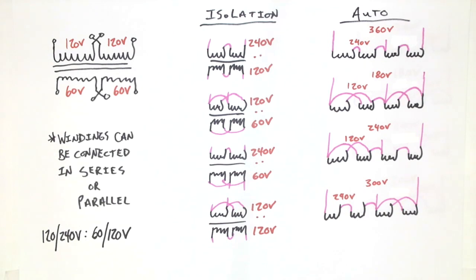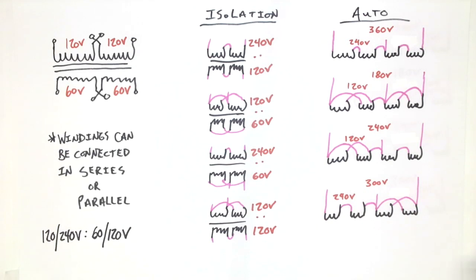Remember, there are voltages outside North America that are much different than what we have for our nominal 3-phase voltage values. And because of that, we need to, at times in the industrial side, choose what type of transformer is necessary to supply voltage to a non-conforming piece of equipment. So if I have a piece of gear that comes in that's rated for 300 volt 3-phase, I'm going to need to use an auto transformer of some sort to get that non-standard voltage.